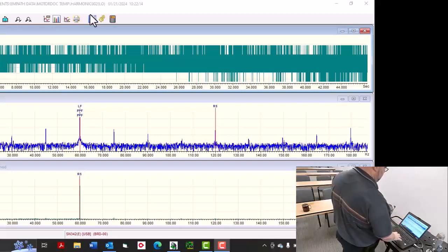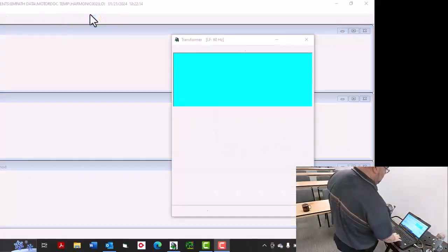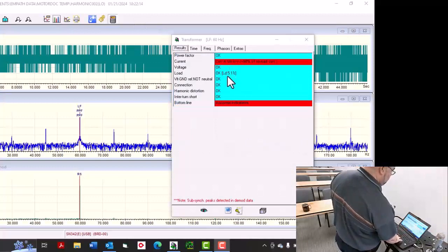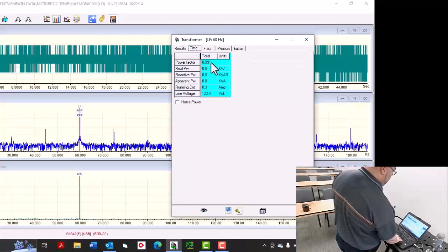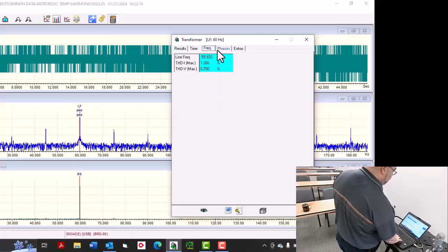Let's go ahead and take a look so we can note certain things. I'm not going to go over to the waveform portion. We're just going to look directly at the end results. Nice and clean. The 15-ish hertz, that always shows up on systems. I haven't set anything up there, so let's take a look and see where we are. So power factor 0.991.